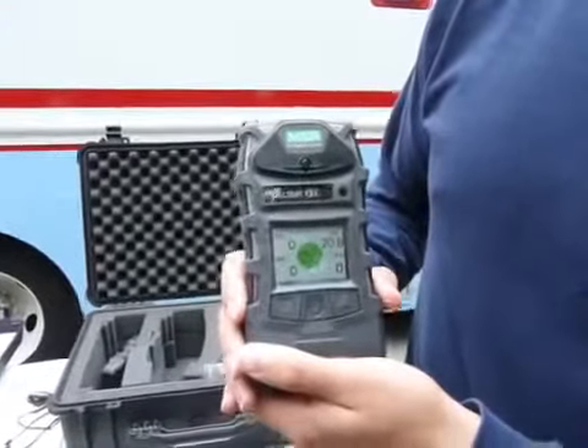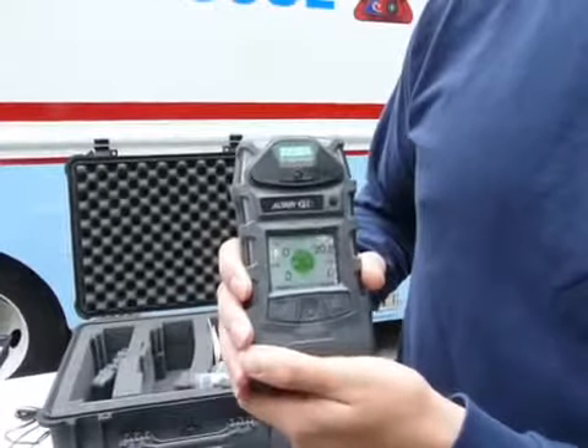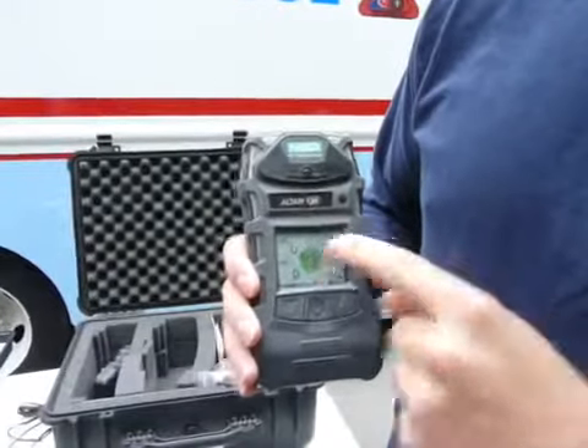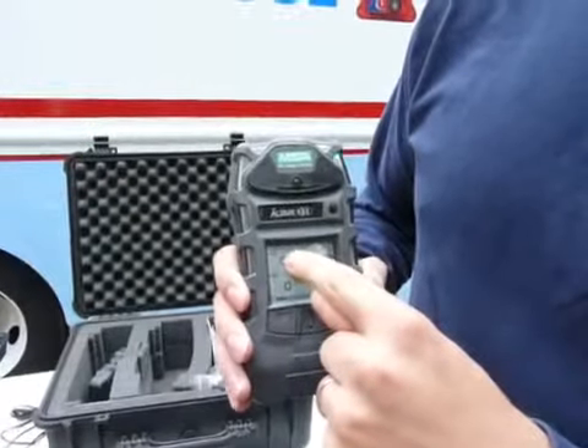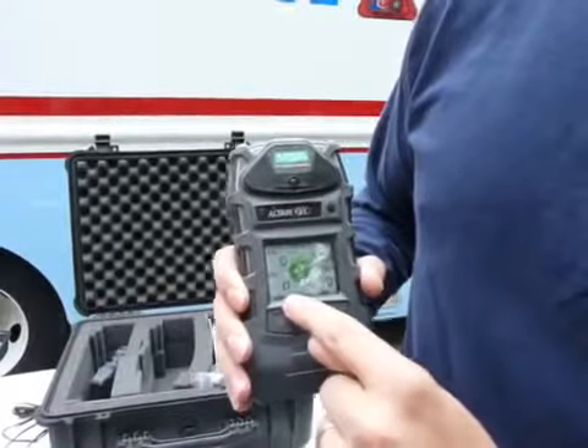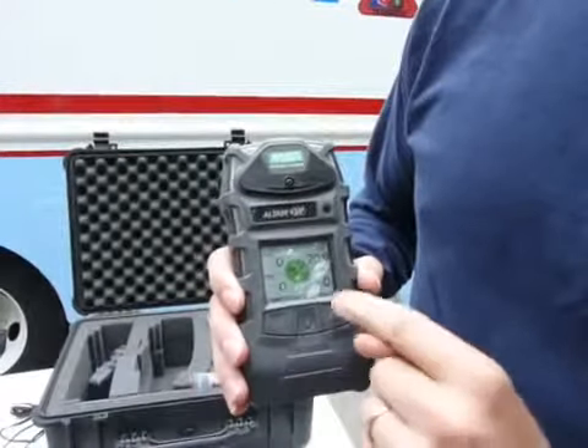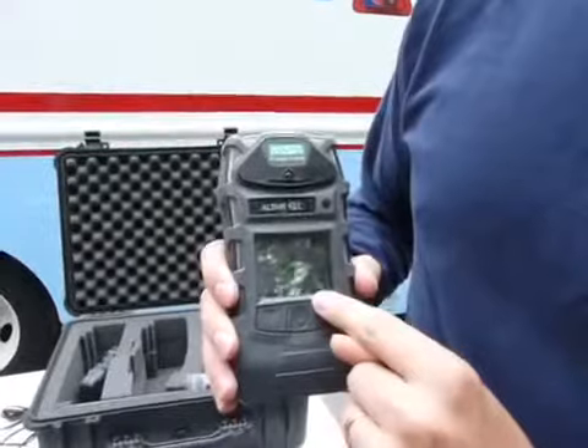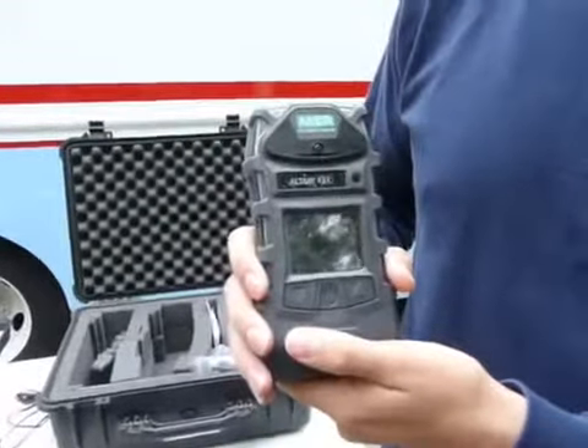Right now, it's just in a normal functioning mode where it's checking each of the different things: percent oxygen, percent lower explosive limit, that's your combustible sensor, your parts per million of carbon monoxide, and your parts per million of hydrogen sulfide. If any of these go above a critical value, the monitor will start to alarm.